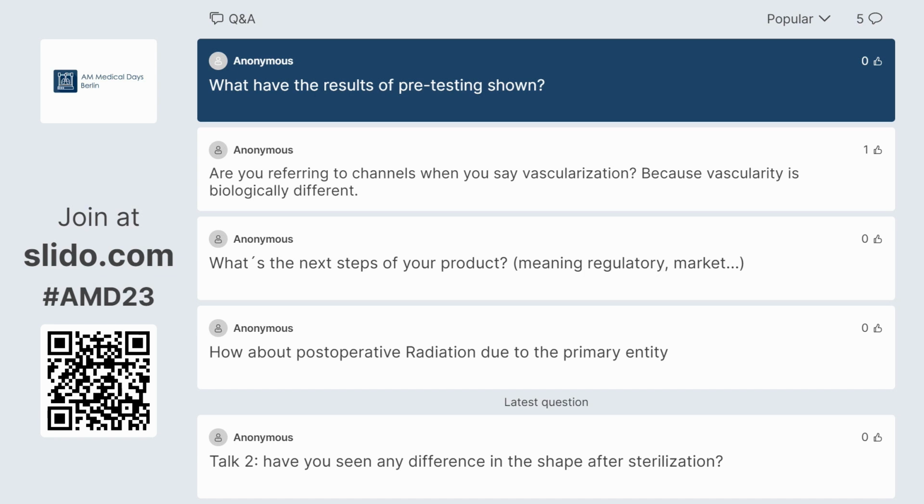So, preclinical tests, regarding regulations, CE or FDA, finally, you have to prove two things. The safety of your product, so you have the whole guidelines of biocompatibility to ensure that your process is safe and the biomaterials induced by your process are safe. And then you have to prove the performance. So the performance shown on the slides here is the regeneration of tissue. So this is one criterion of performance. And the stability of volume after degradation.